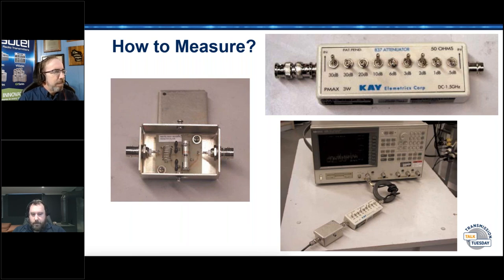The analyzer is a little different now, or at least it was last week when I was down there. Same idea, sort of a switched attenuator, notch filter as required. We'd have that whole signal chain encased in a copper box with a lid with finger stock, and we could screw it down if need be, depending on how noisy it is in the room at the time, because there could be half a dozen transmitters running with some of the loads sitting right next to where you're trying to measure. So depending on how bad the RF environment is, that box is a lifesaver.